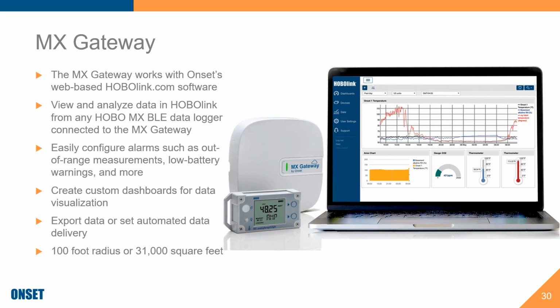A question had come in earlier about flexibility. You do need to start and configure the loggers with your mobile device when working with the gateway. What I typically recommend is that you put the logger into wrap mode, so it overwrites the oldest data and basically keeps running for you.